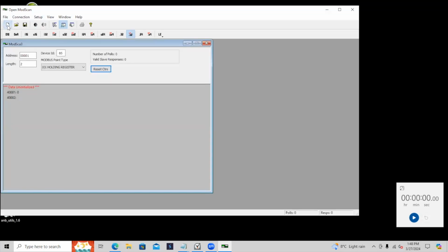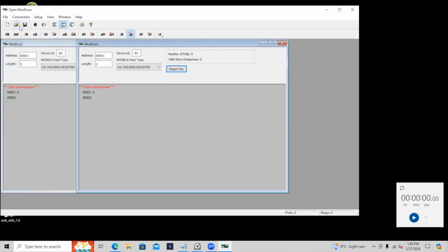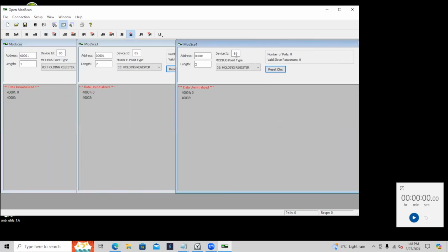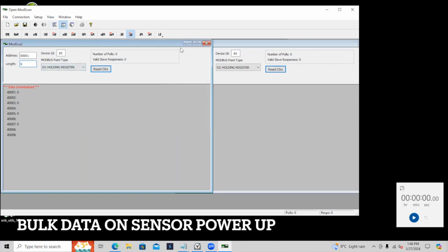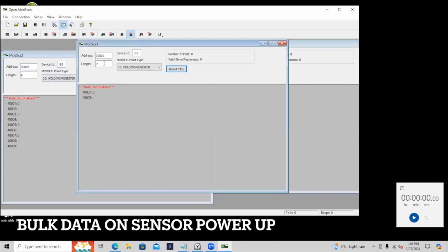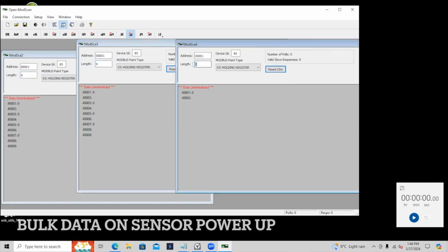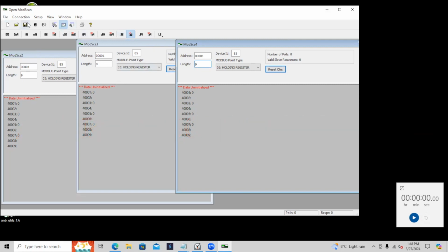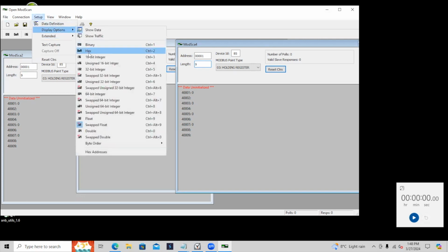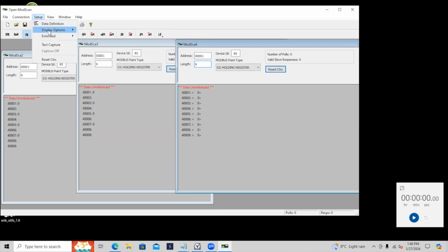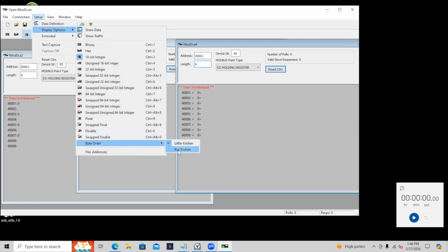In ModScan, we can set up the interface. We just open 3 new windows. So we want to use 3 different types of output to show the sensor in operation. In this case, we'll be using the full data stream, with the call length set to 9. We can then set a window. First, we'll do this one. This will display the transducer health. To do that, we do display options. This is going to be a 16-bit integer, and this has a big endian.